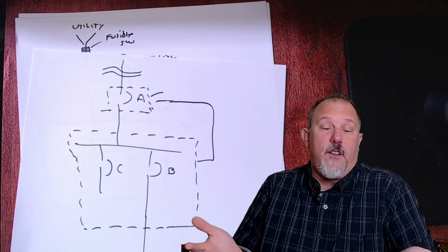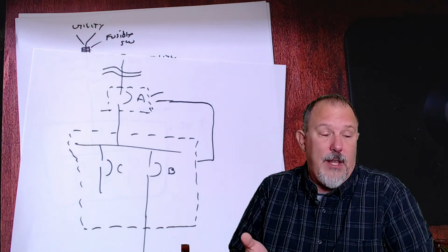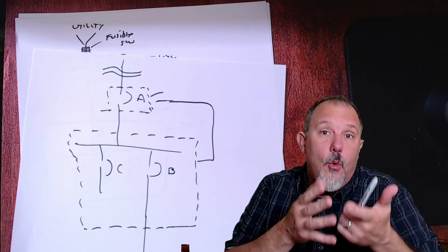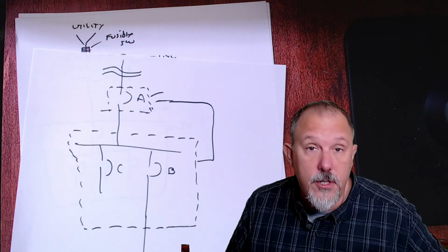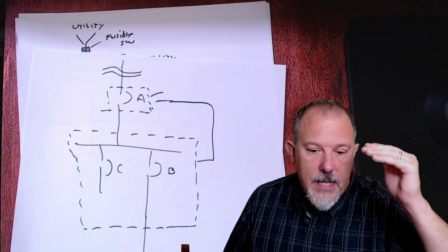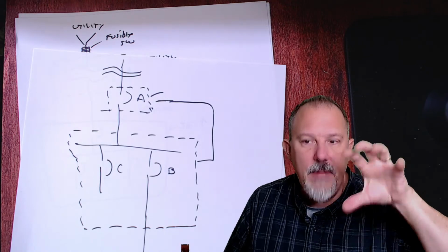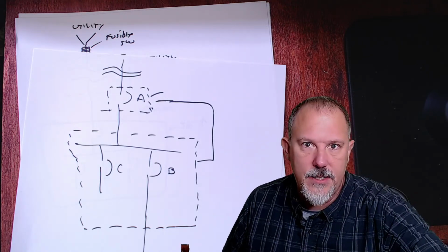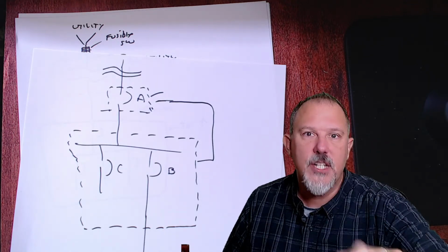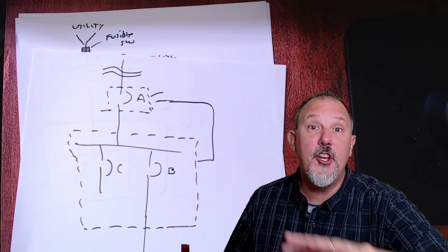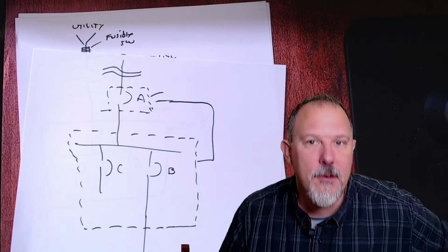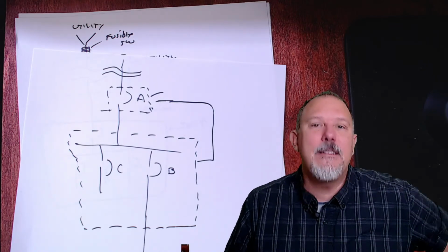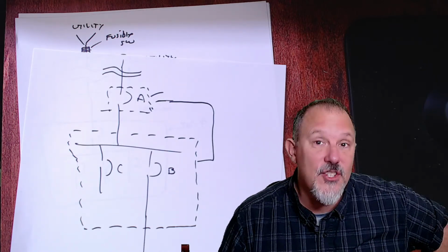Do I not have arc flash issues on medium voltage? Now, one of the arguments that I've heard, which I think is a good one, is that working on medium voltage equipment energized is much less likely. People get nervous around 4160, 13.8 kV. They don't like to monkey with stuff that is hot.